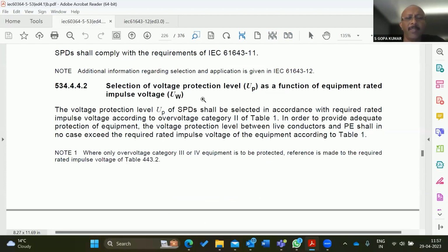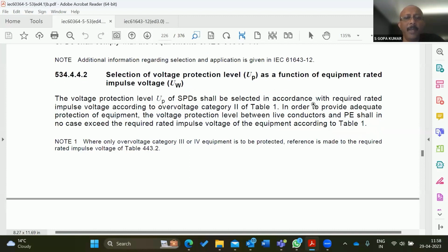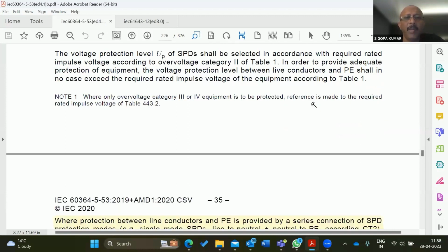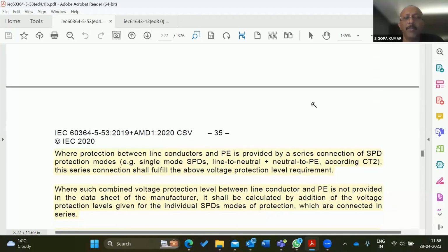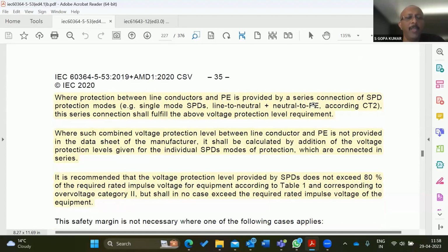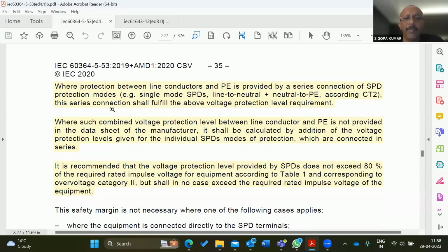Most often, SPDs are installed with long wires. Even though we are repeatedly telling the users to use the shortest wire length, due to practical reasons, due to a fuse in between, sometimes because there is no space in the panel board, SPDs with longer wires are used. And for your information, these SPDs, of course, will not have any effect in the network. It's just like a dummy, keeping something in your network and believing that it will protect your electronics. Technically, it won't do any job. So this important information is included in these lines of the IEC standard. Of course, we have included this in the National Electrical Code as well.